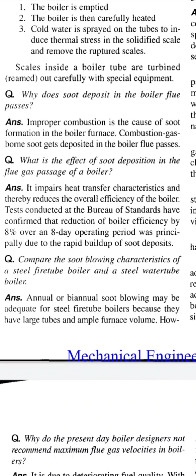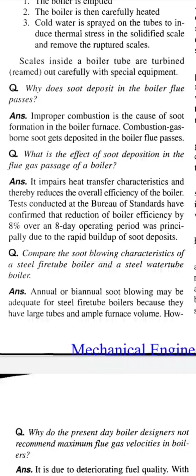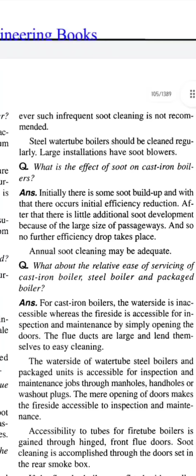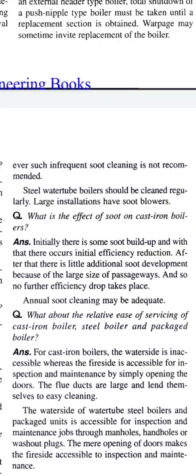Question: compare the soot blowing characteristics of a steel fire tube boiler and a steel water tube boiler. Annual or biannual soot blowing may be adequate for steel fire tube boilers because they have large tubes and ample furnace volume. However, infrequent soot cleaning is not recommended. Steel water tube boilers should be cleaned regularly. Large installations have soot blowers.